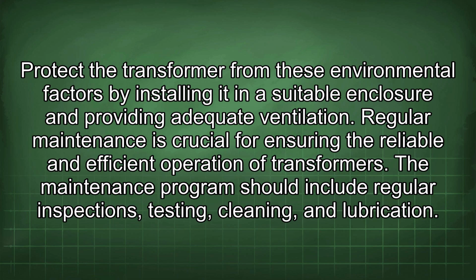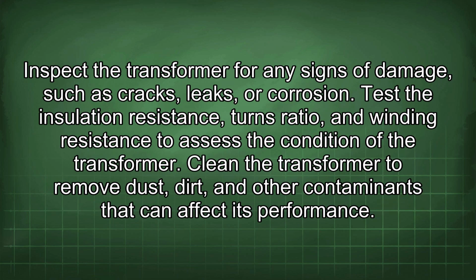Regular maintenance is crucial for ensuring the reliable and efficient operation of transformers. The maintenance program should include regular inspections, testing, cleaning, and lubrication. Inspect the transformer for any signs of damage, such as cracks, leaks, or corrosion. Test the insulation resistance, turns ratio, and winding resistance to assess the condition of the transformer.